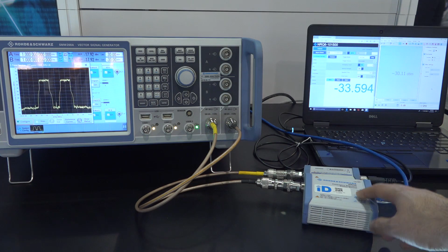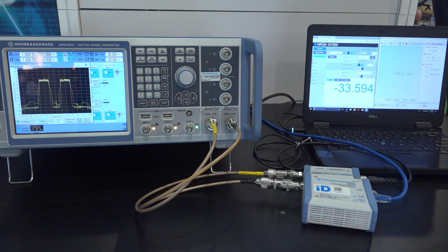And these guys are power over Ethernet, so you can imagine mounting this in a remote area and being able to tune it directly from the Ethernet port and select the channel you're looking at. And of course, the benefits of having external synthesizers connected to it, your own sources connected to it. But the fact that they have managed to preserve the measurement uncertainty while giving you frequency selectivity is huge in a power sensor of this form factor, which I think can be very useful in this type of application.